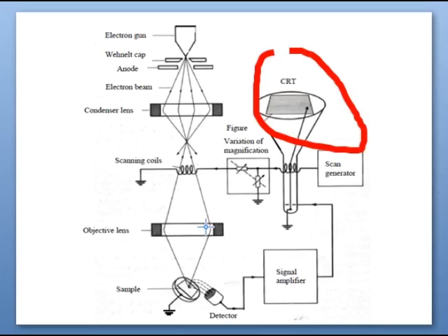Whenever an intricate or deep surface is there, the electron emission will be limited. When the primary electrons hit the component or the surface of the specimen, fewer secondary electrons are generated. Those will produce a darker image, where a higher amount of electrons getting reflected will generate a lighter image.